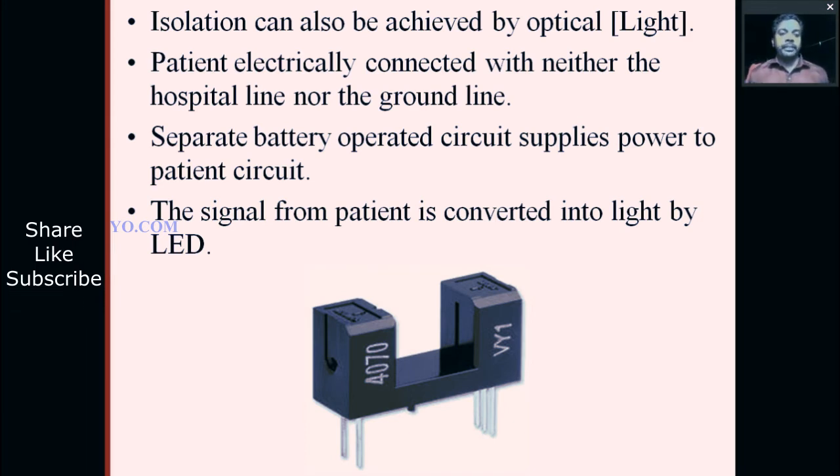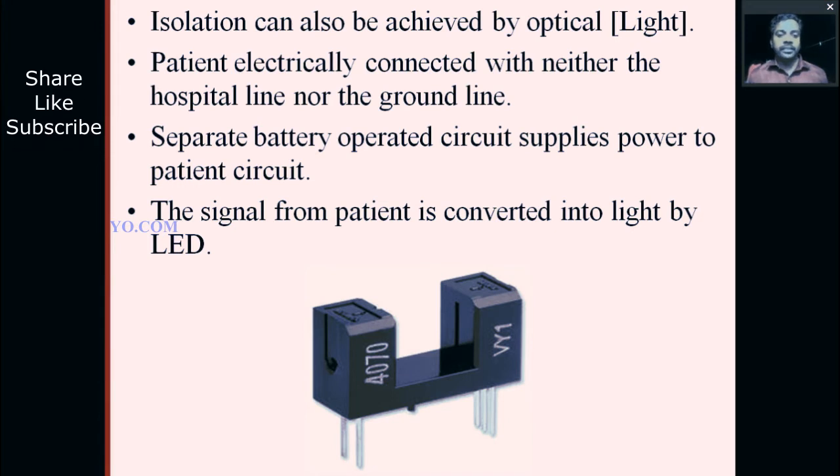The patient is not electrically connected to the hospital ground line, nor to the high voltage line or the ground of any circuit. The patient is not connected electrically. A battery operated circuit supplies power to the patient side.